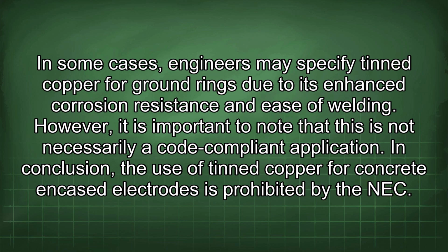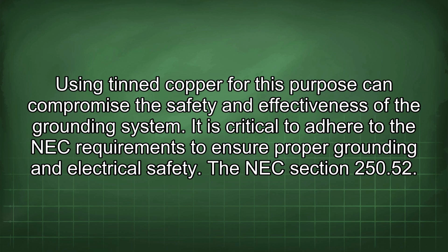In conclusion, the use of tinned copper for concrete encased electrodes is prohibited by the NEC. Using tinned copper for this purpose can compromise the safety and effectiveness of the grounding system. It is critical to adhere to the NEC requirements to ensure proper grounding and electrical safety.